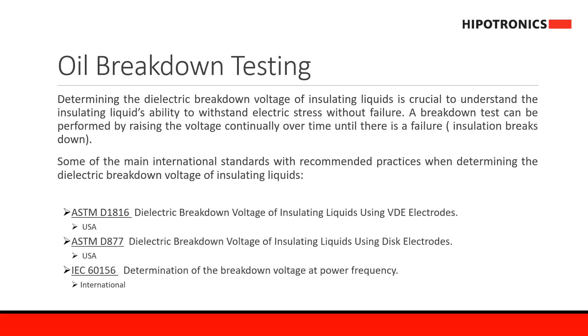For oil breakdown testing, you want to put the oil to a stress test until it actually fails. The breakdown test can be performed by raising the voltage continually over time until there is an actual failure. The main standards used in the US are the ASTM D1816 and the ASTM D877. The ASTM D877 is starting to be phased out, and we're focusing more on the ASTM D1816, while the international community follows the IEC 60156.